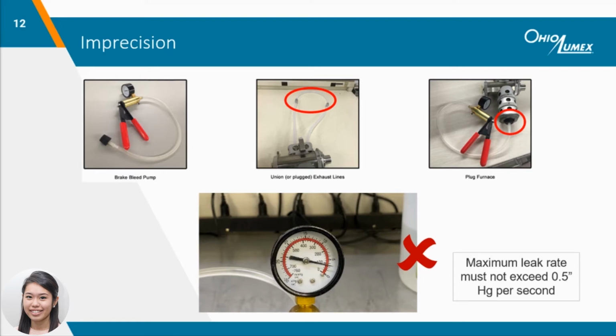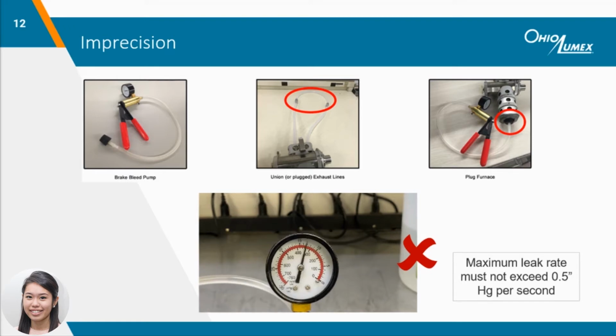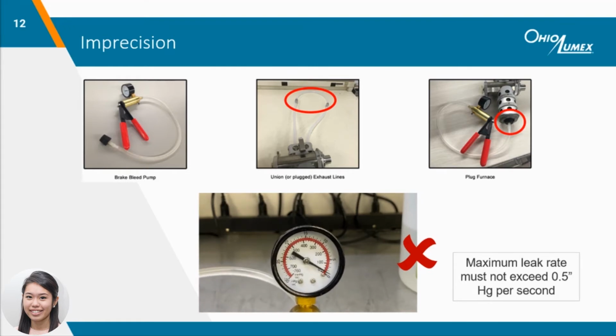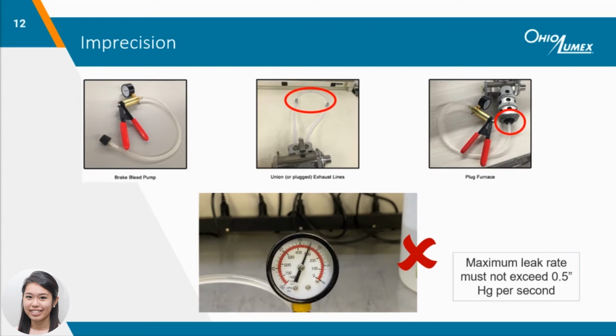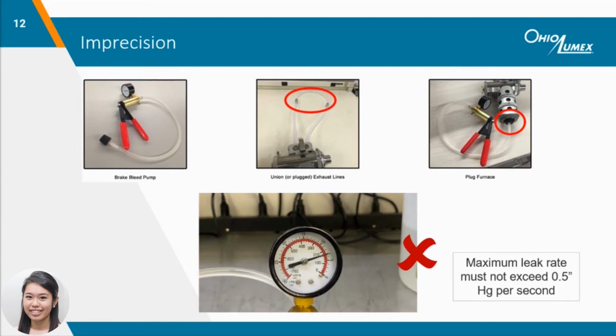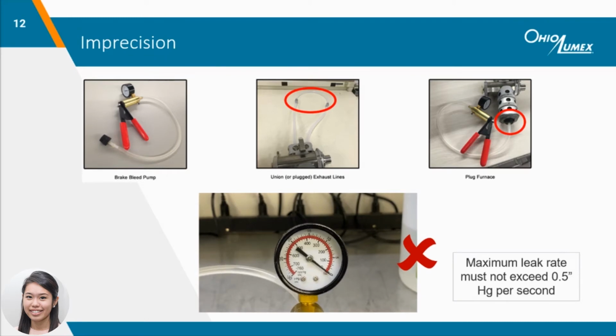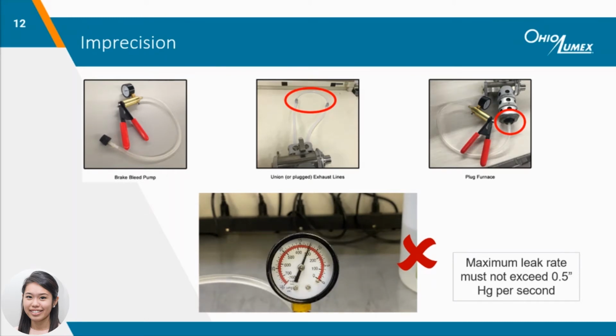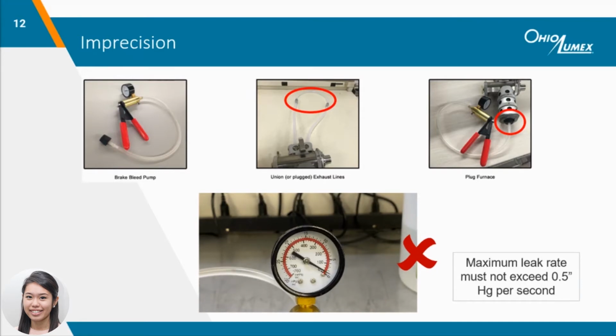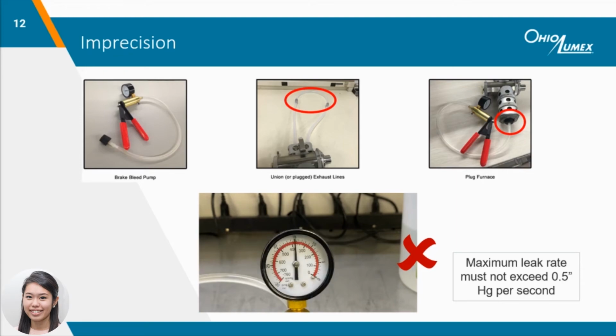If there is any difficulty maintaining a vacuum, graphite gaskets can be used on both sides of the window to create a better seal. A leak can also occur at the silicone exhaust hoses, since they can harden over time and occasionally crack. These lines can be replaced at any time. After the leak check, ensure the Viton O-ring is placed between the heater cartridge and the attachment.